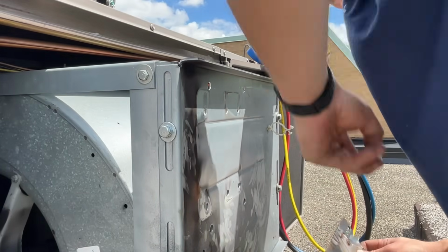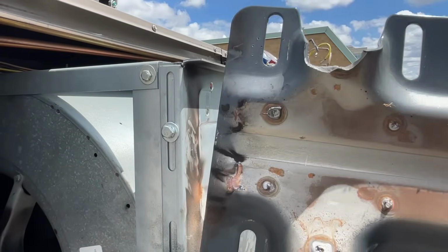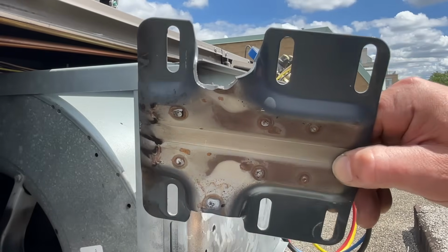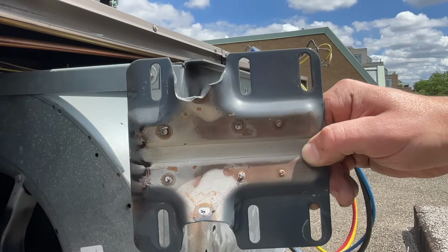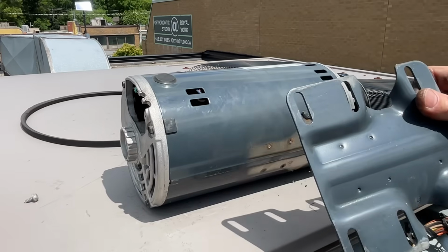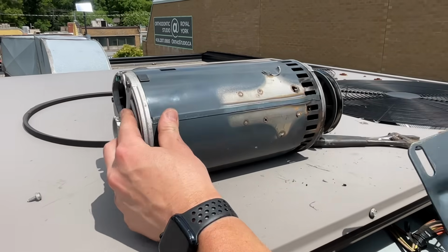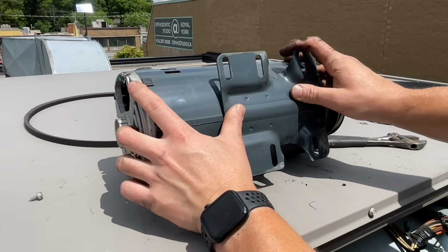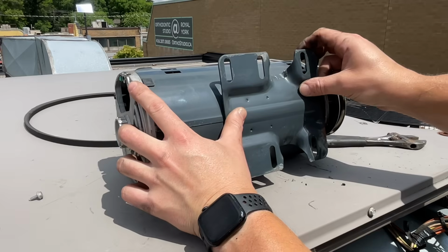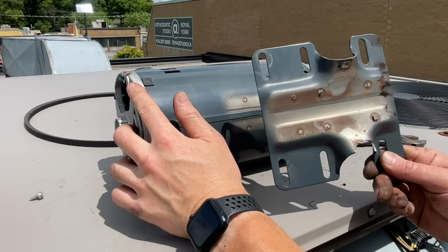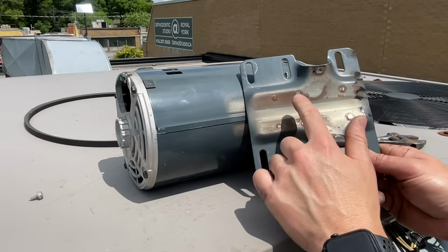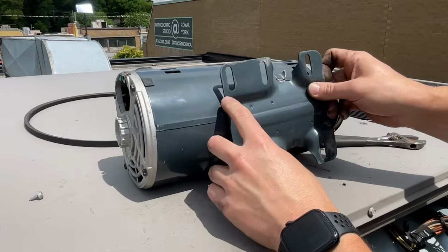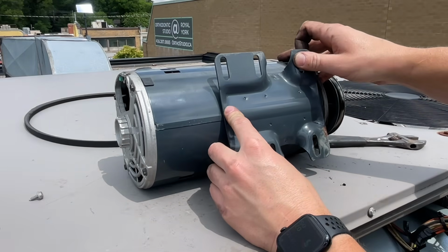All right, let's take a look at this. There's our broken bracket. Snapped clean off. All our spot welds went. Let's quickly take a look at this. So there was our bracket. Here's our motor. At one point in time, she sat on there just like that. And like I said before, I've never seen that happen before. How many welds do they have here? 1, 2, 3, 4, 5, 6, 7, 8. 8 welds, and this thing just ripped clean off.